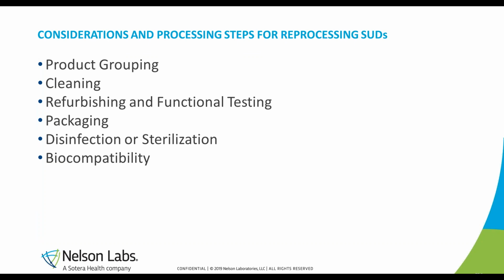As discussed earlier, reusing devices intended for single use without having the correctly validated process in place may have a detrimental effect on the patient's health. Considerations for reprocessing will typically follow a similar format to the manufacturing of the original device. These include product grouping, cleaning, refurbishing and function testing, packaging, and disinfection or sterilization, and finally, biocompatibility.